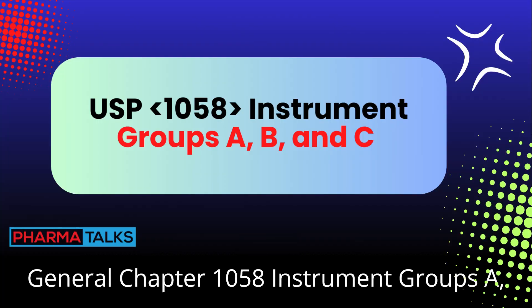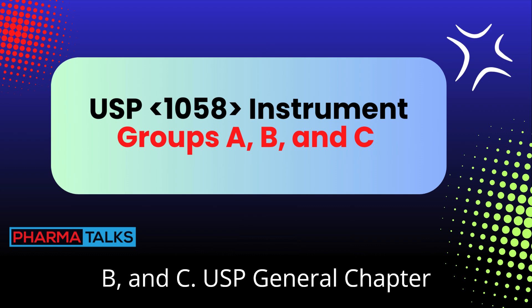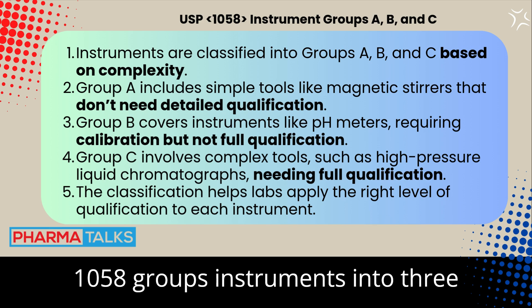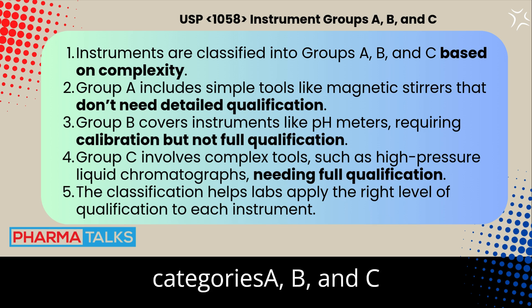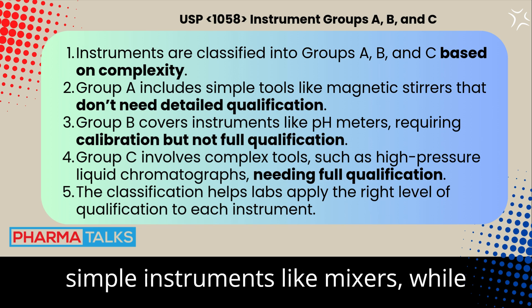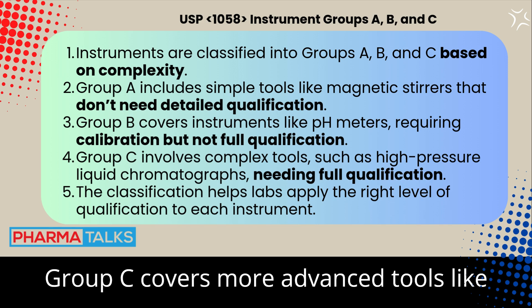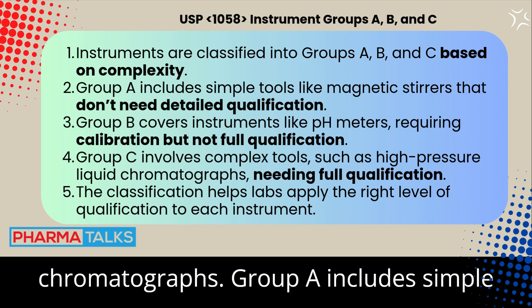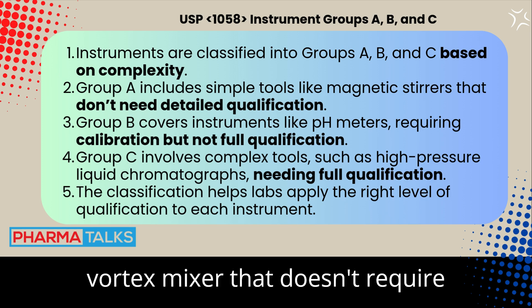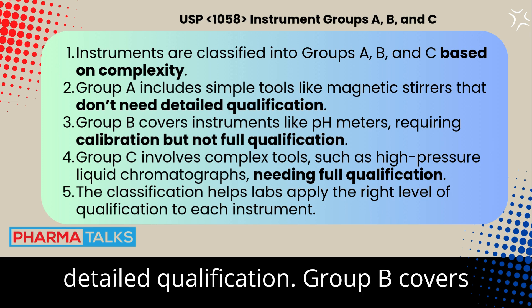USP General Chapter 1058 groups instruments into three categories — A, B, and C — based on complexity. Group A includes simple apparatus like a magnetic stirrer or vortex mixer that doesn't require detailed qualification, while Group C covers more advanced tools like chromatographs.